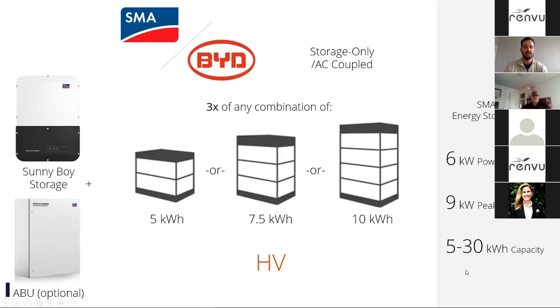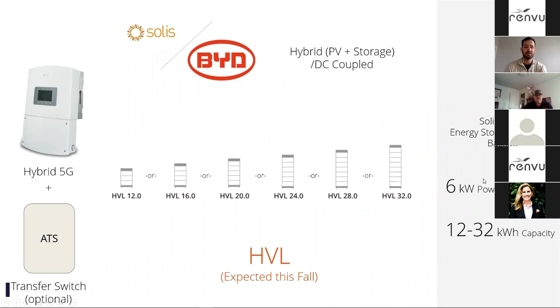Jumping into our HVL with Solis, which is expected to launch this fall. The expectation is based on certification. We don't consider a product pairing launched until, of course, we've worked out all the compatibility, but also certificates. We get UL 9540, which is the system level certificate for these products together. So similar combination as our HV: battery, inverter, transfer switch, and then a battery. You can see a nice wide range of sizes here, 12 all the way up to 32. So the resulting output is 6 kilowatts of power, 12 to 32 kilowatt hours of capacity.